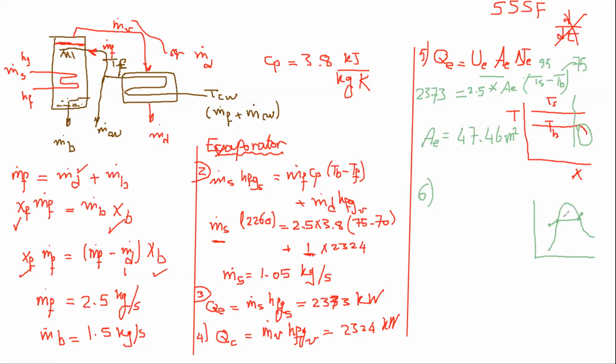We did some research work, maybe more than 10 years ago, looking at the effect of desuperheating and subcooling on the performance, and we found that this effect is negligible. So it is safe to neglect these and just assume that it is basically latent heat, which is just HFG.